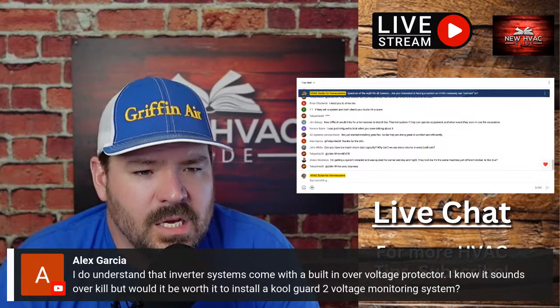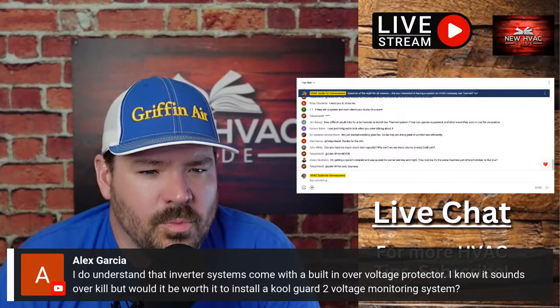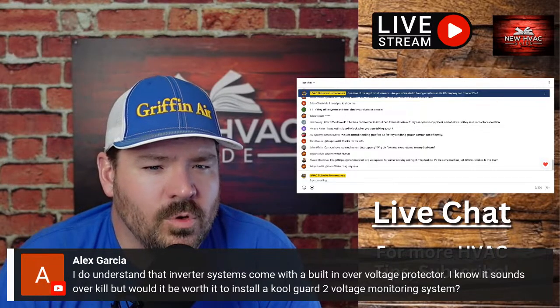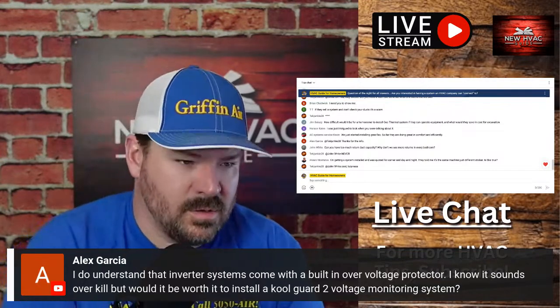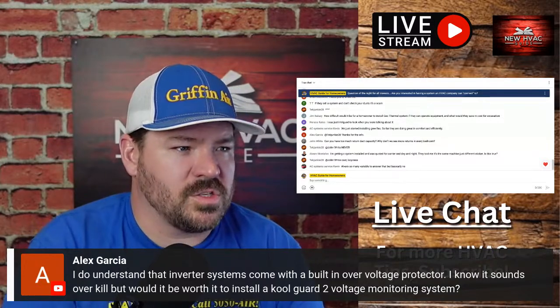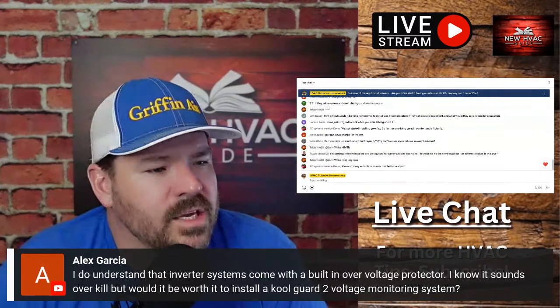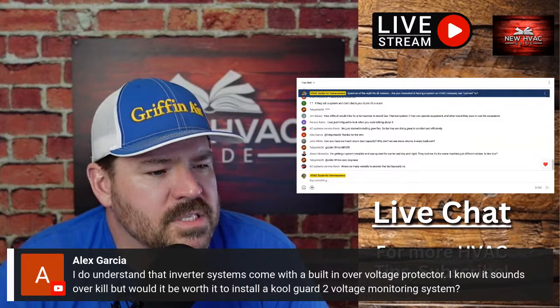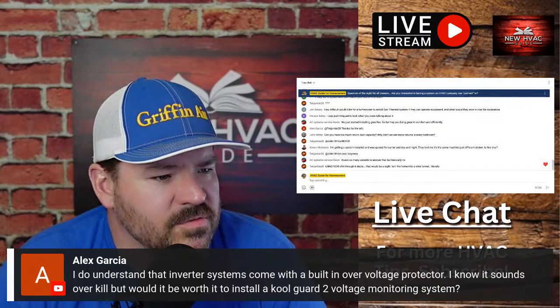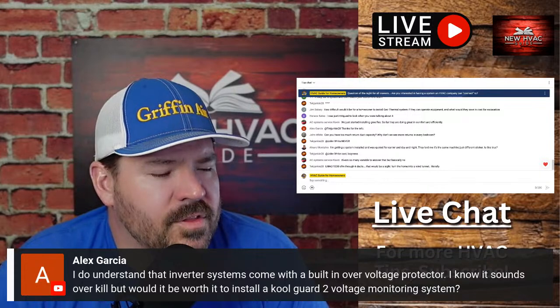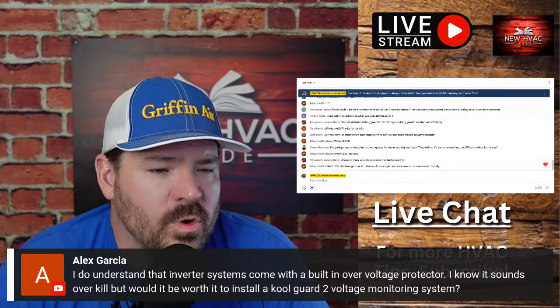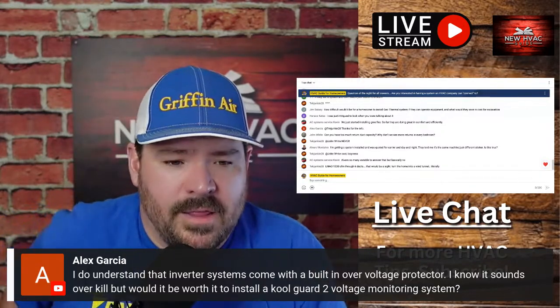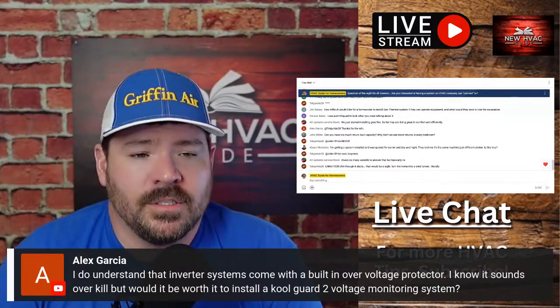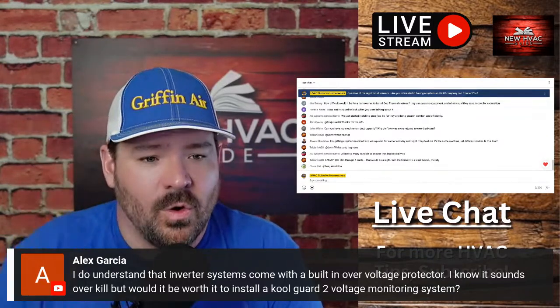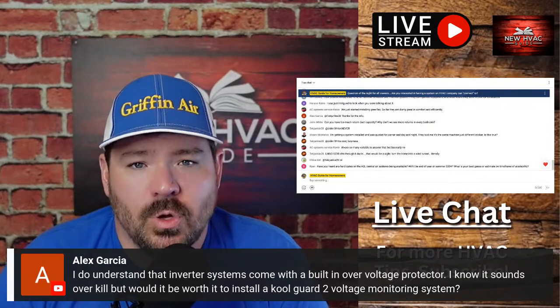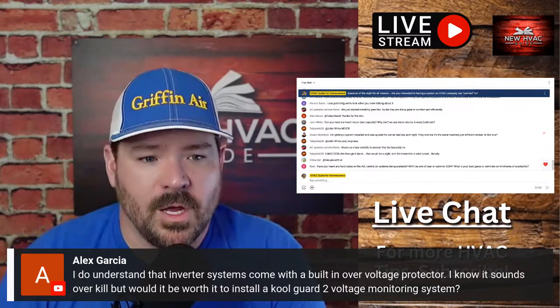I understand that inverter systems come with a built-in overvoltage protector. I know it sounds overkill, but would it be worth it to install a Kool Guard 2 voltage monitoring system? Let's see—I'm not familiar with that product, so I'm looking it up. Is that a phase monitor? It looks like it says voltage monitor. If it does the same thing a phase monitor does—it says voltage monitoring and surge protection—then those are a good idea, especially for an inverter system. We've had inverter systems with board failures. One time in particular, we had a board fail, and two weeks later the same board failed on a multi-zone mini split. The manufacturer told us, hey, we're going to give you this part again under warranty, but you need to get a phase monitor installed on that system.